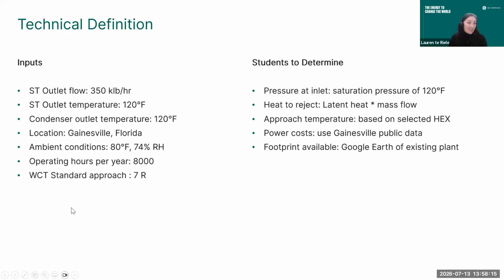Some information about the problem statement: what we've given you is the outlet conditions of the steam turbine. Unfortunately this is in imperial units—often in the US these come in imperial, so be prepared for unit conversions. We have 350,000 pounds of steam per hour coming into your condenser at 120 degrees Fahrenheit. We should assume saturated conditions, and the full focus of your condenser is to condense.